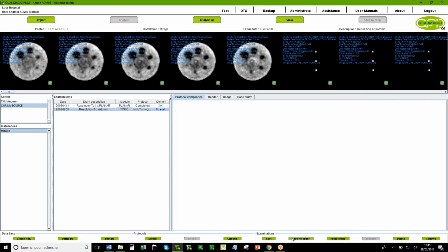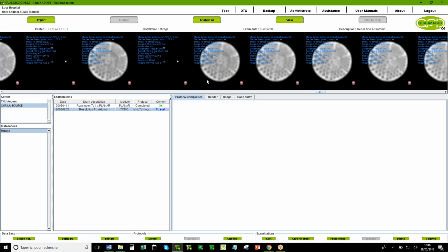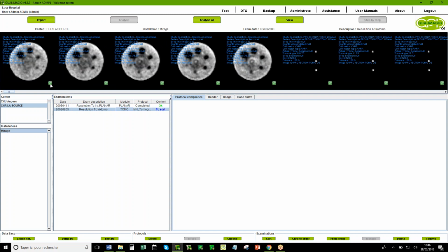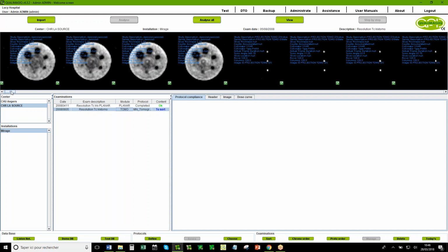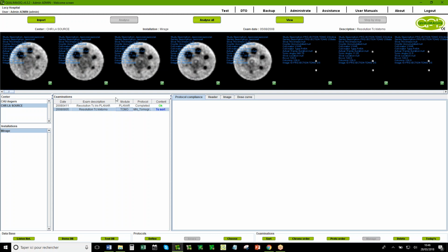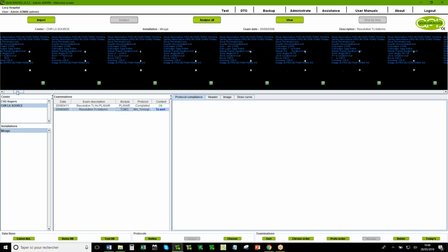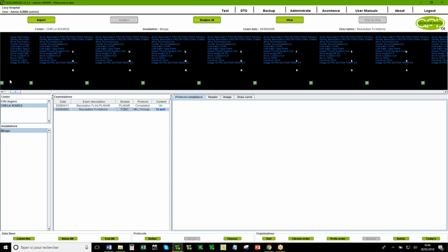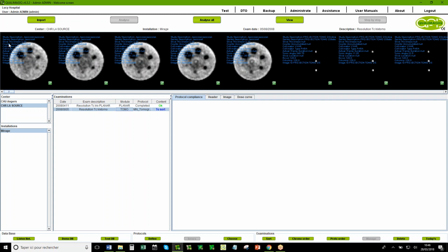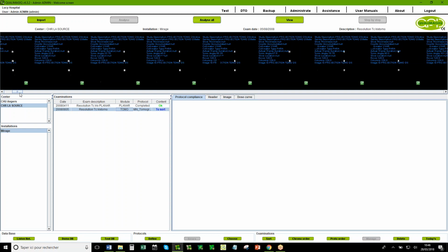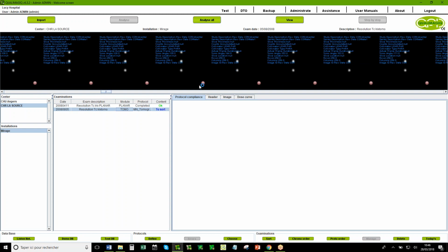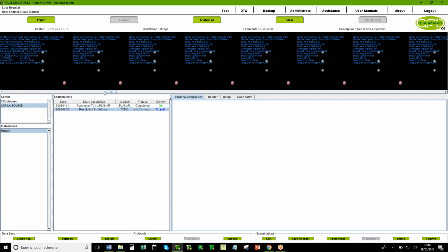So now the last, and it's very fast compared to planar, for example. So now we are in tomographic mode. In tomographic mode, they use a Jaszczak phantom first, and they do a complete acquisition of the JASAC. So you don't have to select which images you want to evaluate. The software knows, and the software proposes to analyze these 5 slices and to remove the rest. The red one, the software proposed to remove.